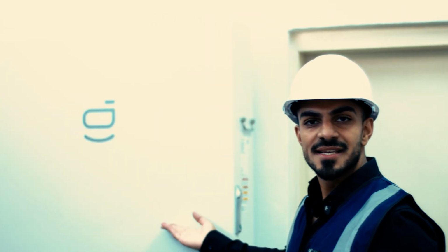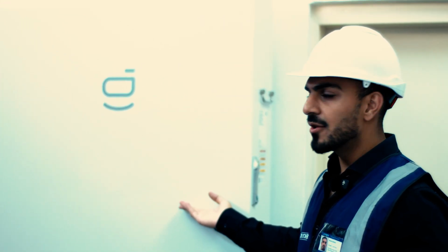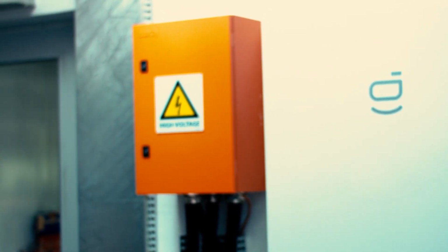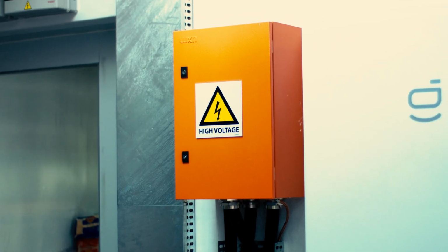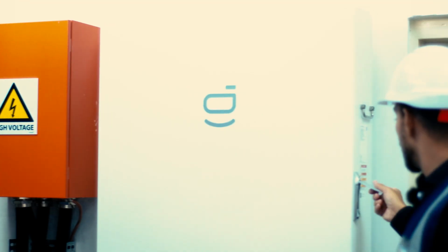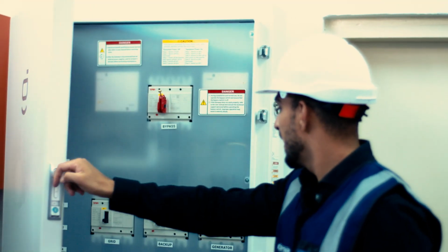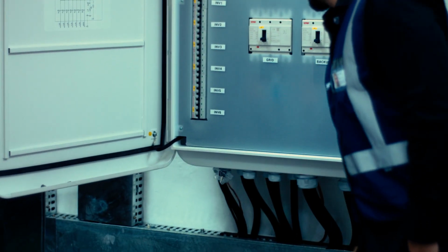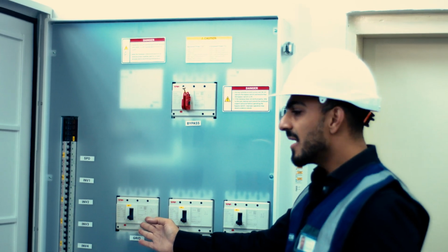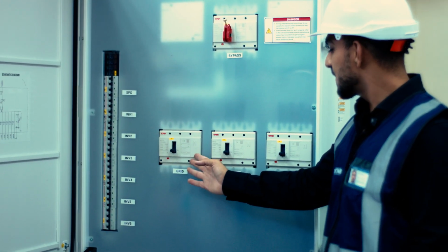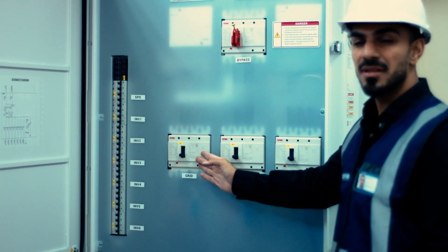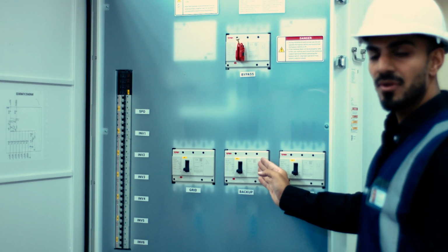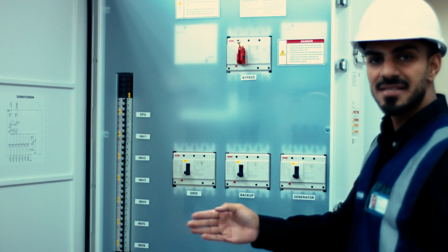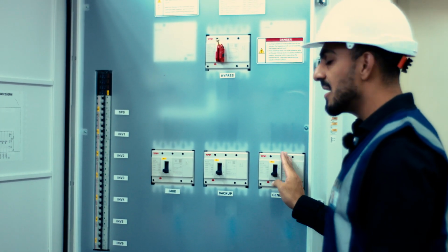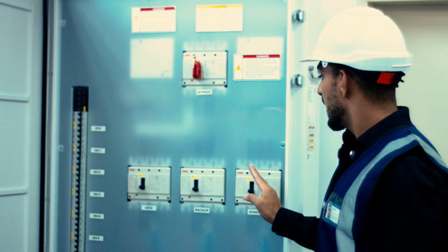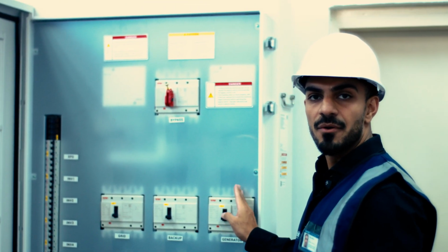Over here we have the Sigenergy 120 kilowatt gateway, and next to it our changeover box. The first thing we're going to do is open up this gateway and show you what's inside. We've got our grid circuit breaker, which supplies mains power to the system. We have our backup port, which sends power back from the system to the loads, and our generator port, which supplies generator power to the system.